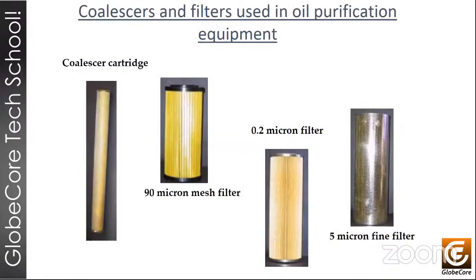For example, coalescent filters are capable of removing some moisture. They're not particularly used with transformers since they don't have the necessary absorption rate to reach the levels that we're looking for. Secondly, they're easily depleted or saturated rather, and the cost associated with using such type of filter can run quite high. Other cartridge filters may differ in micron rating, so we can have 90 micron filters or, for example, 0.2 micron filters. These are usually paper filters from different manufacturers, and these filters allow us to remove particles of certain sizes. I would like to note that these filters will usually clog with time and with use, and that will create pressure inside the filtering equipment, so that's something to look out for.